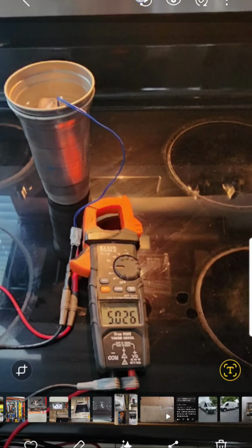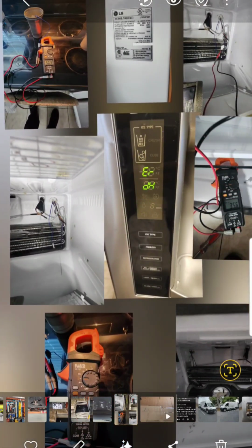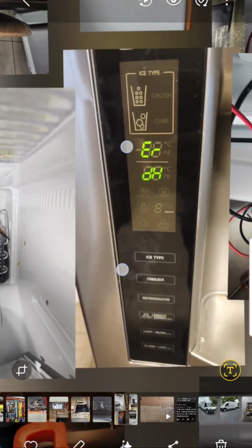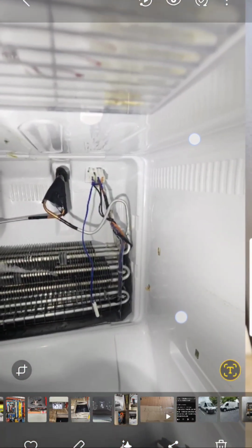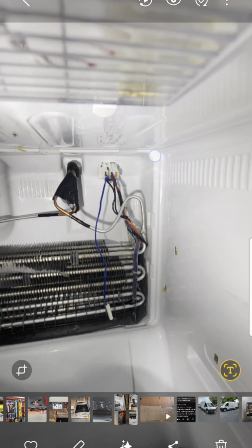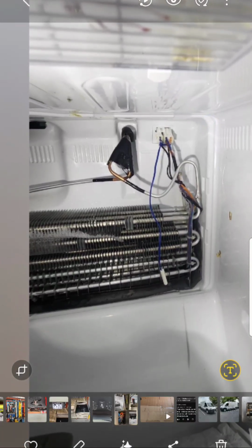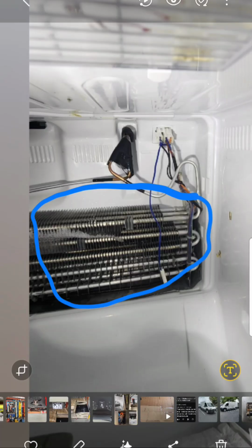Another thing that you could check. Alright, I want to show you. See if I can get it close up. When I took the rear panel off of the freezer compartment to get to the evaporator, as you can see, you want to check to make sure that your evaporator is not built up with ice. As you can see, this one is pretty clean. It's not covered with ice. Usually if you have a legitimate defrost issue, you'll have a lot of frost build up around that evaporator there.